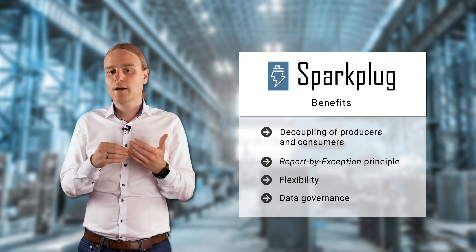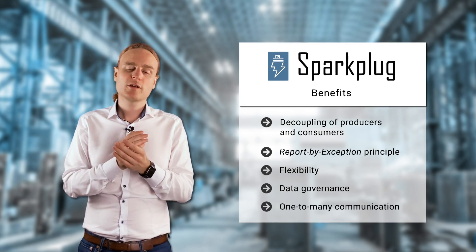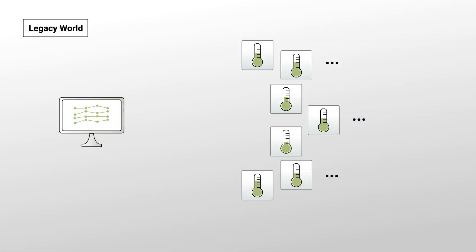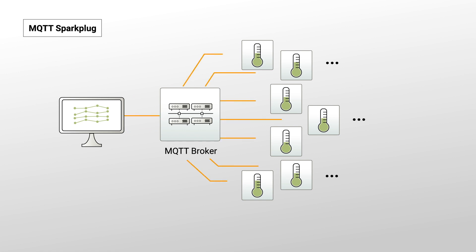And there is one-to-many communications. Every time data is published to the infrastructure, multiple applications can consume that information. In the old legacy world, different systems would pull the same sensor or the same PLC multiple times, causing unnecessary load. With Sparkplug, you send the data once to the MQTT infrastructure and can have multiple consumers — one data packet in, and you could get 10 data packets out, however many you need.